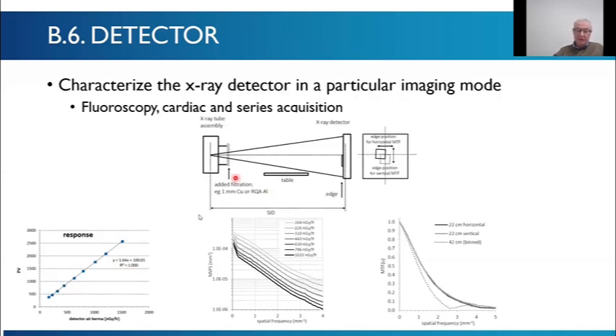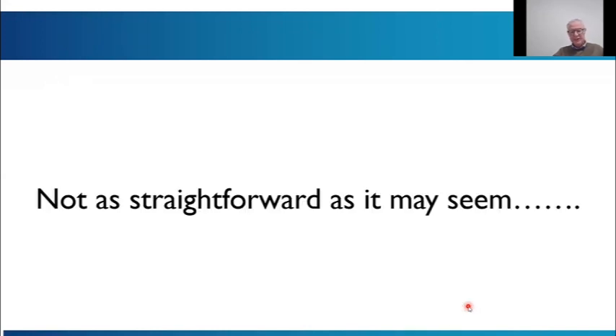And then you can also do it laterally if you want. And then you get the graph like this, like a response function where you have your pixel value versus the air kerma that you vary at the X-ray detector, your noise power spectrum, which you can measure at repeated states throughout the life of the detector to see how the noise is changing quantitatively in the X-ray system. This works very well in mammography, so I don't see why it shouldn't work in dynamic imaging. And then there's the MTF, and here you can see the influence of binning. So here's normal smaller fields of view, and here's the large field of view which has binned. So these are useful detector characterizations, but it's not as straightforward as it may seem to measure this.